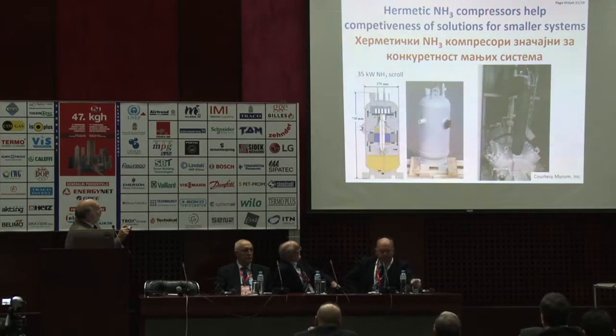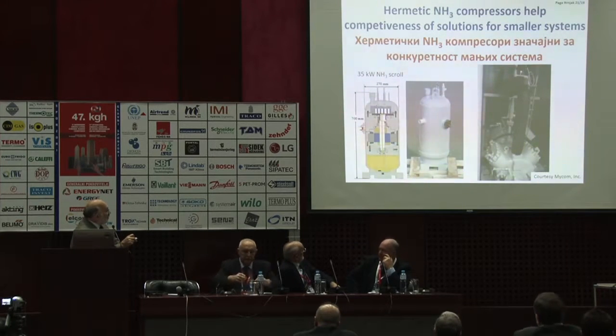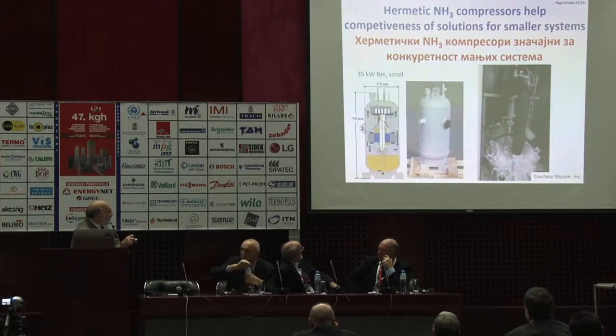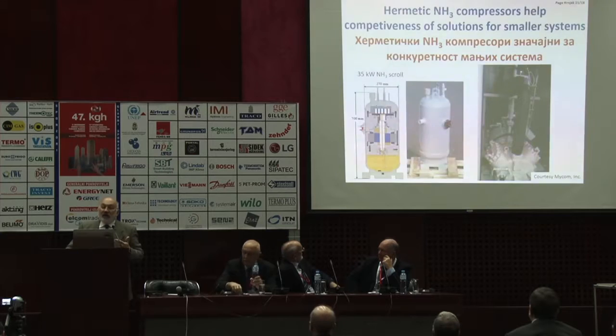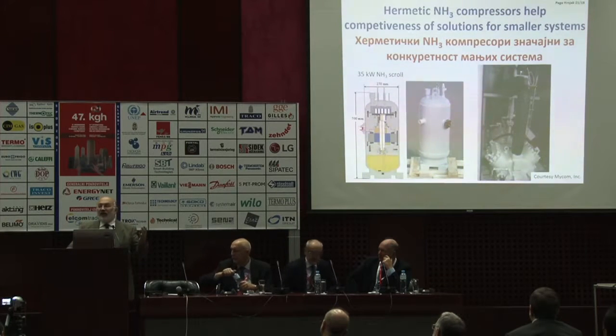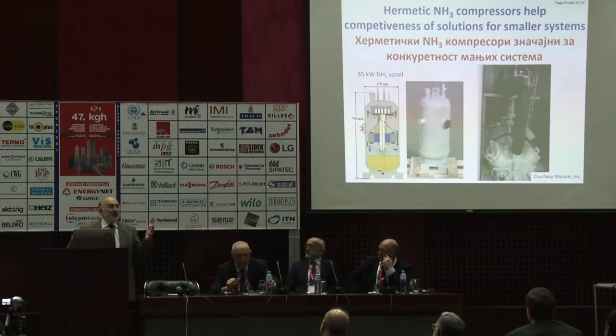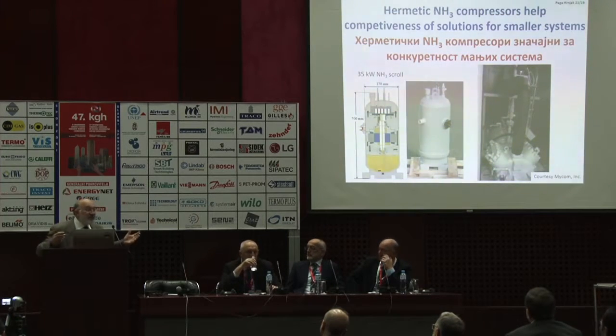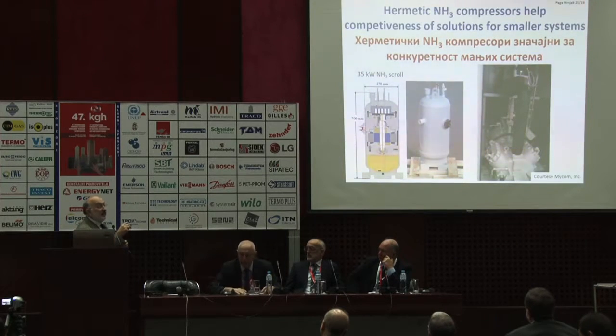What else is happening new? Hermetic ammonia compressors are helping, in my mind, solutions for the smaller ammonia hermetic systems, because with these hermetic compressors, either scroll as presented here or reciprocating with hermetic compressor, it is possible to make a chiller identical to an R22 chiller that behaves the same as an R22 chiller, it acts the same, and it just has ammonia, which is definitely extremely low, if not among the lowest GWP refrigerants, and probably the highest efficiency.